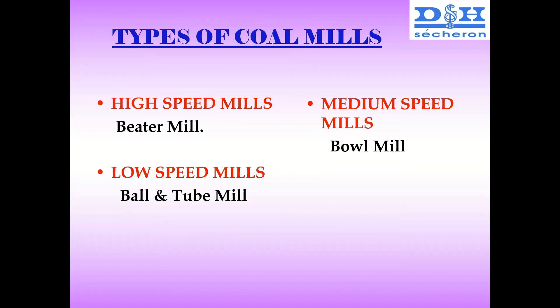In high-speed mills, there is a beater mill, but the capacity of the mill is very less, making it difficult. Low-speed mills are ball-and-tube mills, but the size of the equipment is very large. That is the reason medium-speed bowl mills are mostly preferred and in use today.